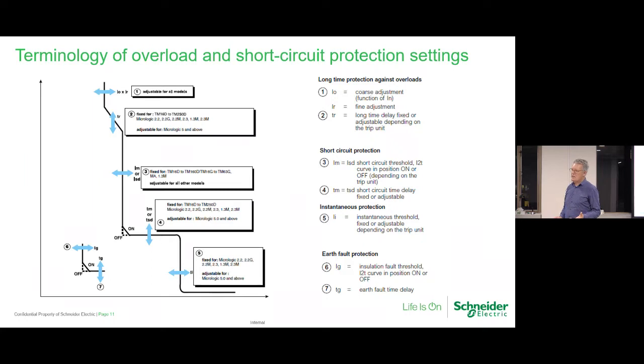Whenever you go into a switchboard or you've designed something and see a circuit breaker, that area is often set either far too low or far too high. It's better to set it as tight as you can based upon what your prospective fault level could be. Don't always push it out, because if you're pushing it out, that means under fault conditions it can potentially see a higher fault than it needs to. So all that connected equipment, cable, etc., is likely to be impaired at a greater current value than it needs to. So that setting is important to get right.